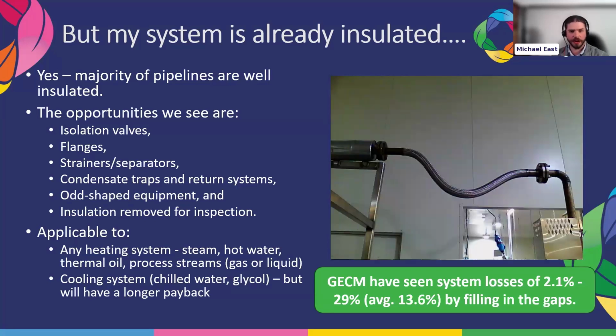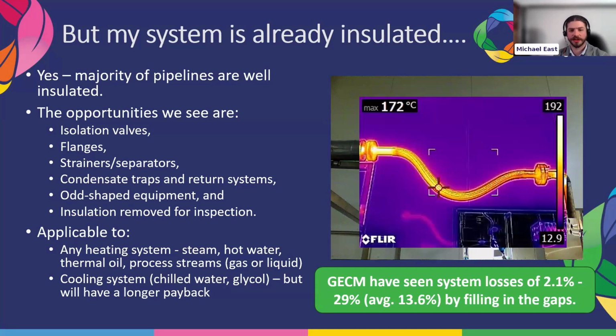Likewise, with this strange flexible coupling, you've got some rigid piping at the end that's got insulation on it, but this flexible union is a little bit tricky to put cladding on or wrap around insulation, and it's sitting at 172 degrees. This one's actually installed in a refrigerated plant, so you've got the thermal energy coming through the fossil fuel system that you're paying for once, and then paying for it again for the refrigeration unit to use electricity to take it out of the room again.